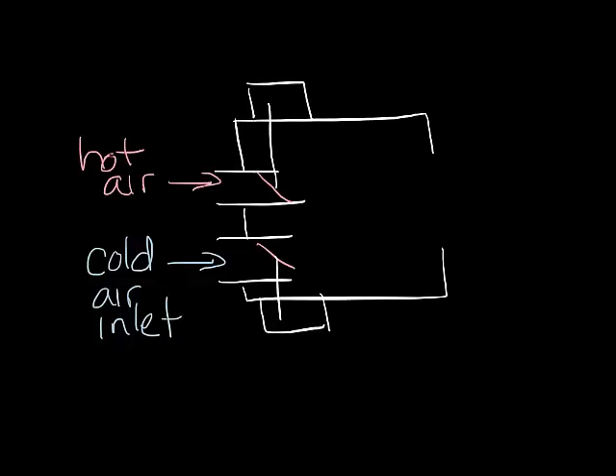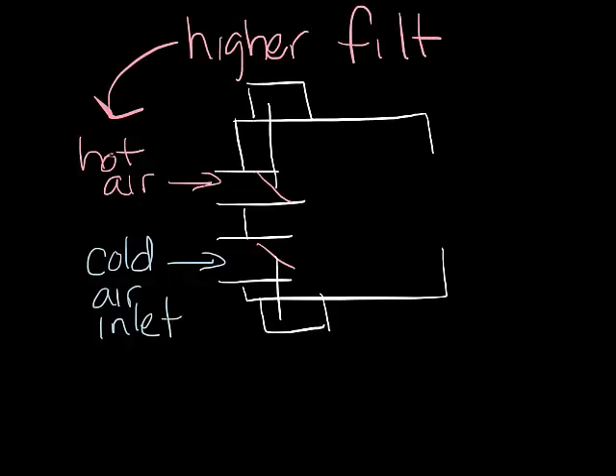The difference is the dual duct has two supply inlets ducted to the supply air system. One is ducted to cold air and the other is ducted to hot air. Like the single duct or fan boxes, each inlet has a damper that controls the amount of airflow that goes through the inlets. One benefit to supplying hot air instead of having reheat coils is that you can filter the supply air at the air handler. For instance, you might have a hospital that would want to provide filtered hot supply air instead of pulling plenum air into the space like you would with a fan box.